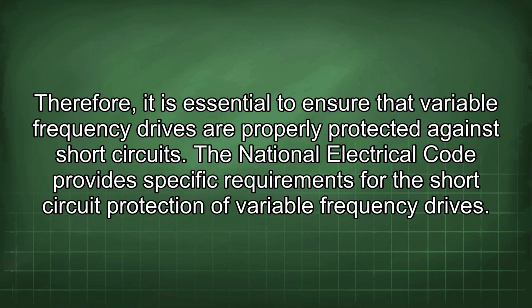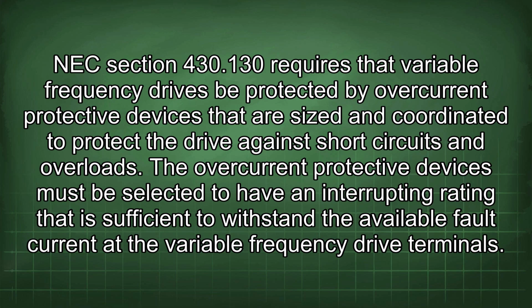The National Electrical Code provides specific requirements for the short-circuit protection of variable frequency drives. NEC Section 430.130 requires that variable frequency drives be protected by overcurrent protective devices that are sized and coordinated to protect the drive against short circuits and overloads. The overcurrent protective devices must be selected to have an interrupting rating that is sufficient to withstand the available fault current at the variable frequency drive terminals.